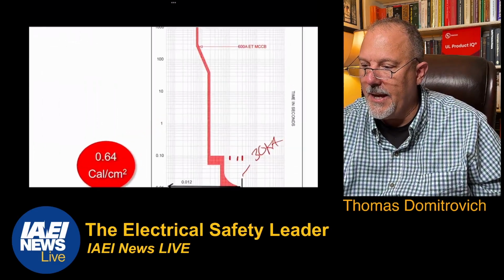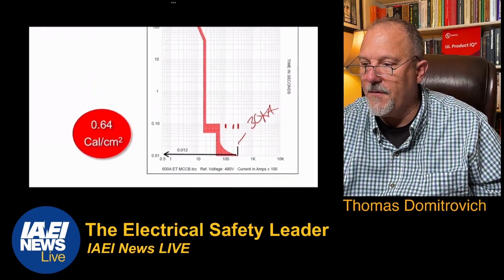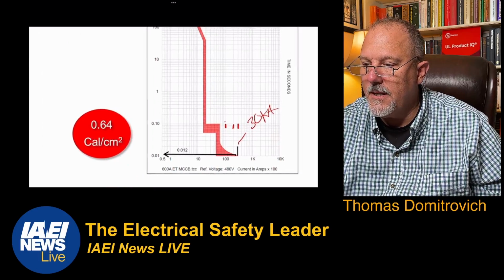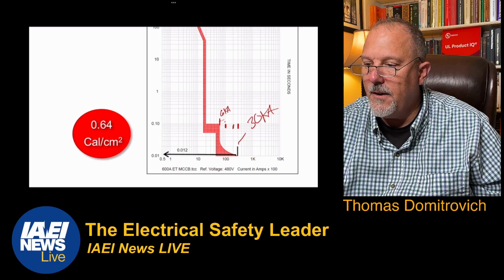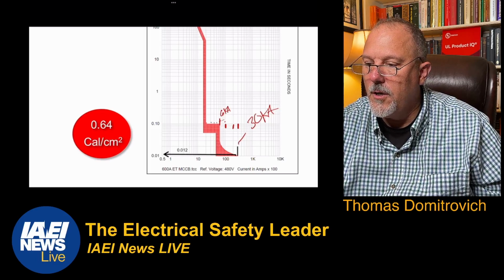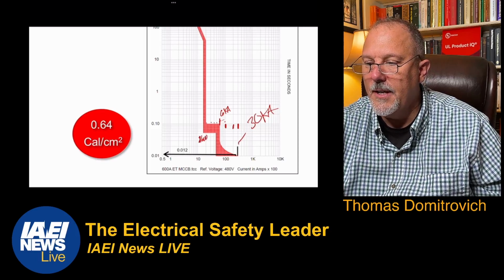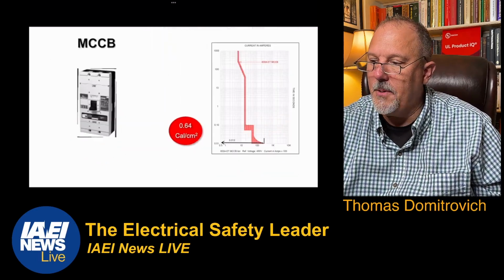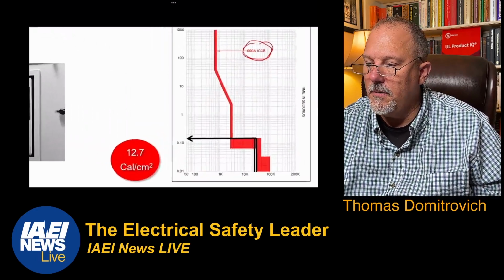This short time delay picked up around, if this is 10,000, that's 9, 8, 7, 6,000 amps. So that's 6,000 amps. 5, 4, 3, 2, I don't know, maybe 2,600, about 1,600 amps, something like that, is where my short time delay picks up.